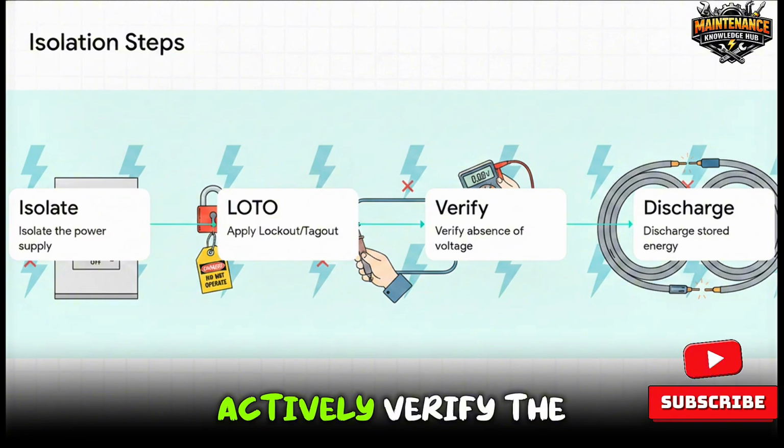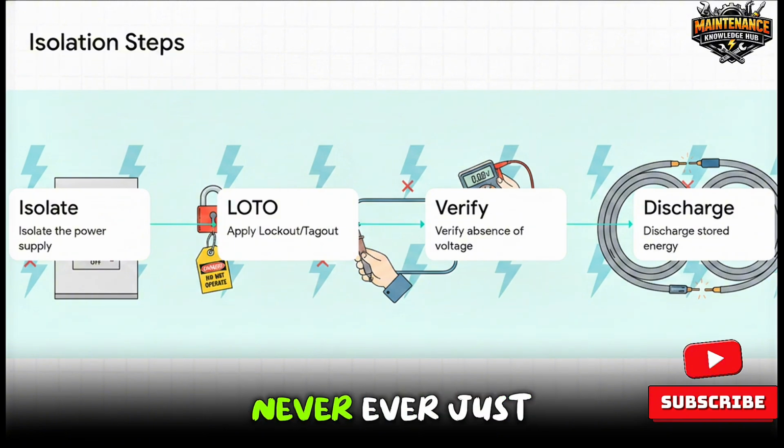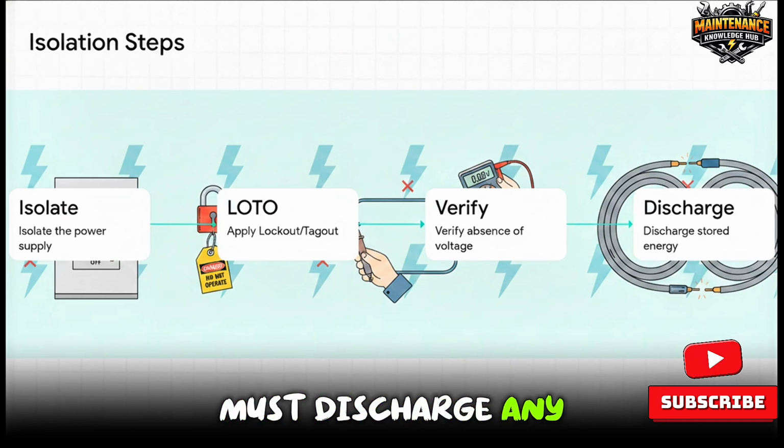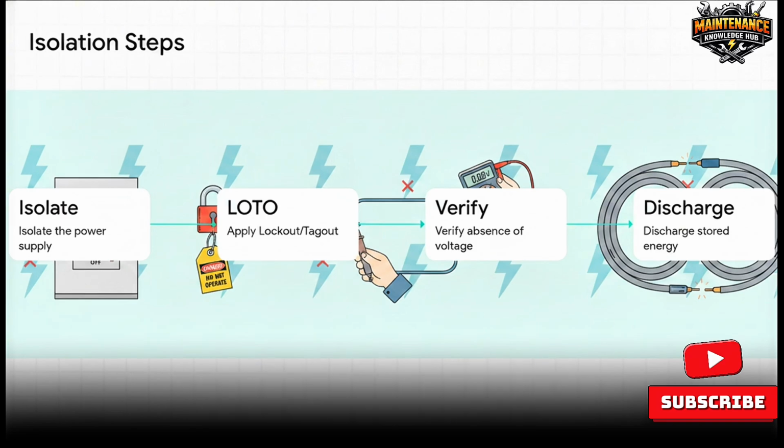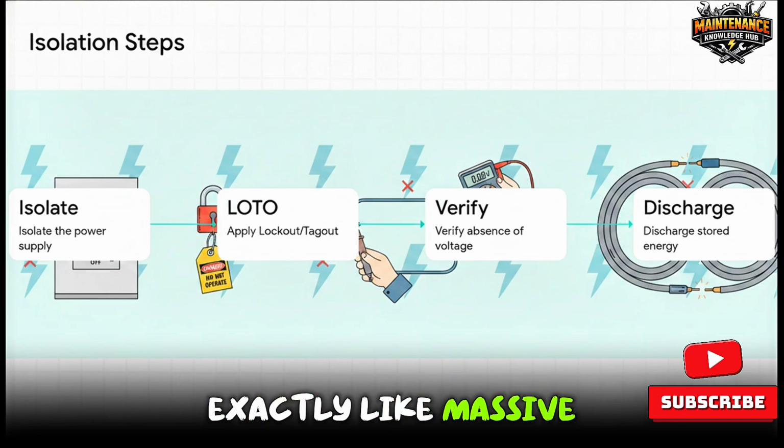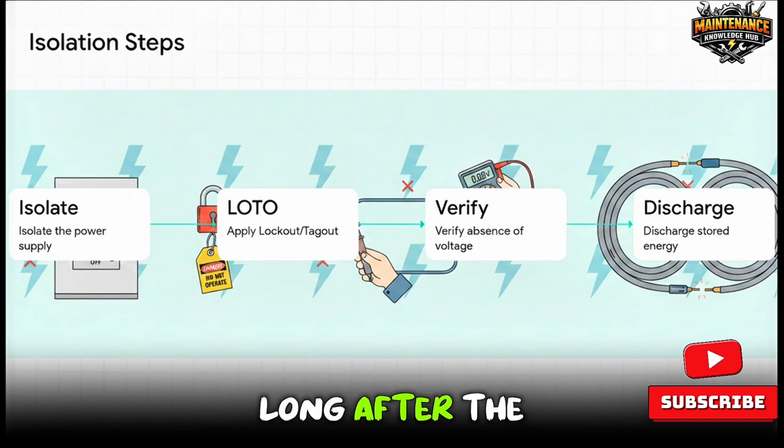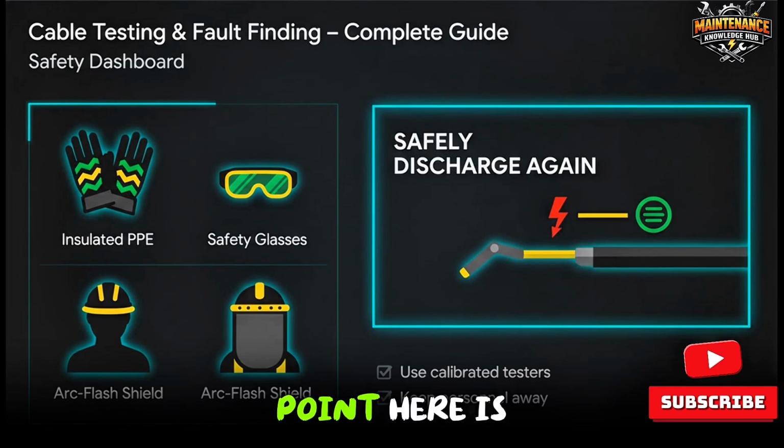Third, you have to actively verify the absence of voltage with an approved calibrated tester. Never, ever just assume the power is off. And fourth, you must discharge any stored energy before handling the cables. Long cables act exactly like massive batteries, and they can hold a lethal charge long after the power is cut. So the crucial point here is preparation. It's what keeps you alive.